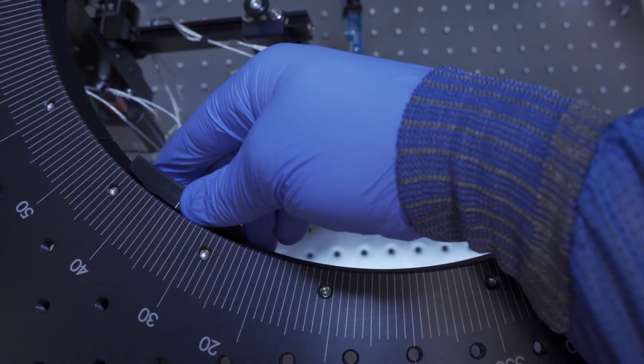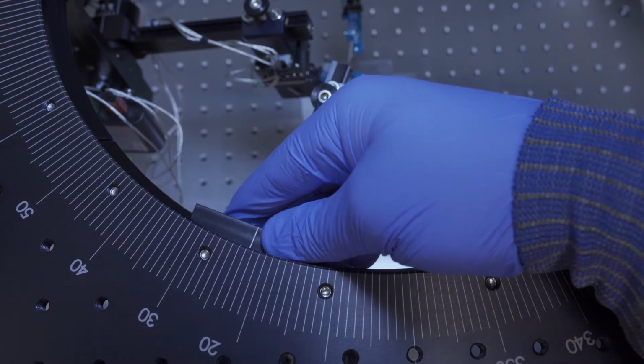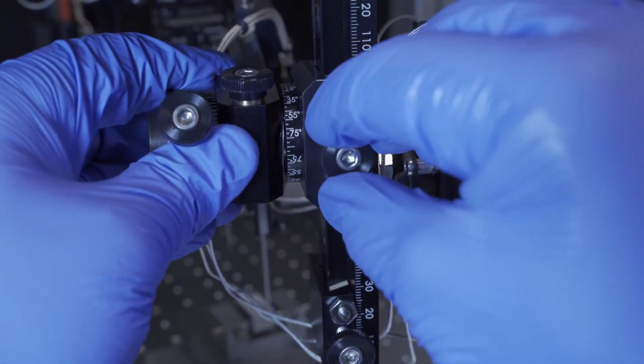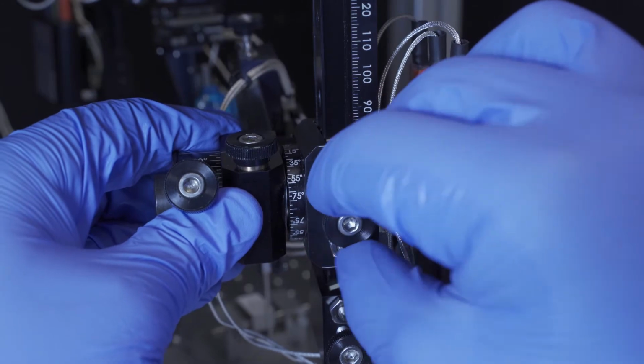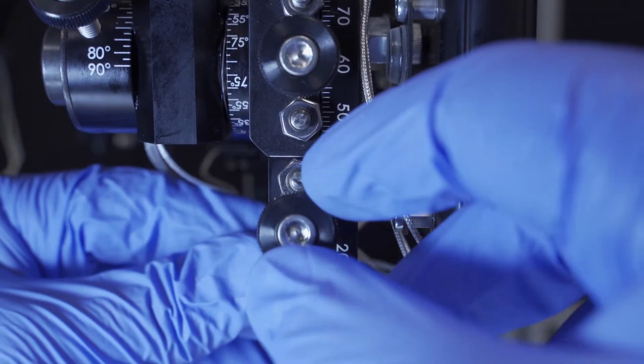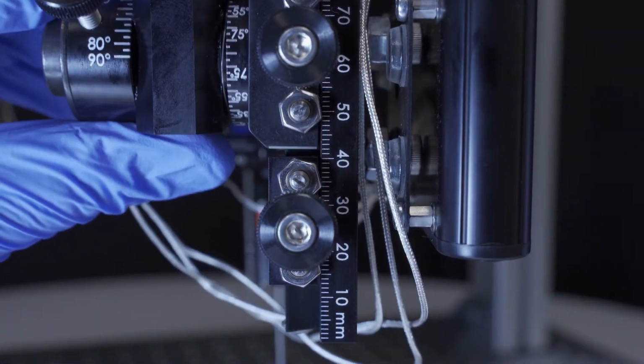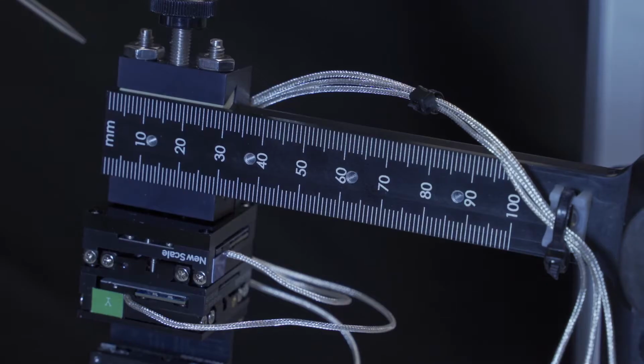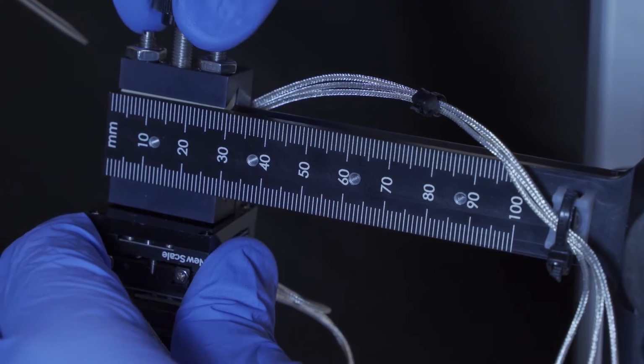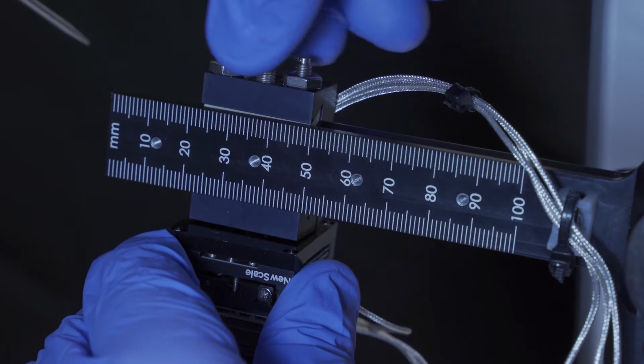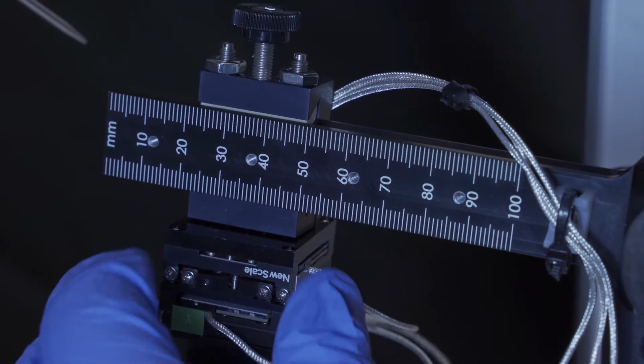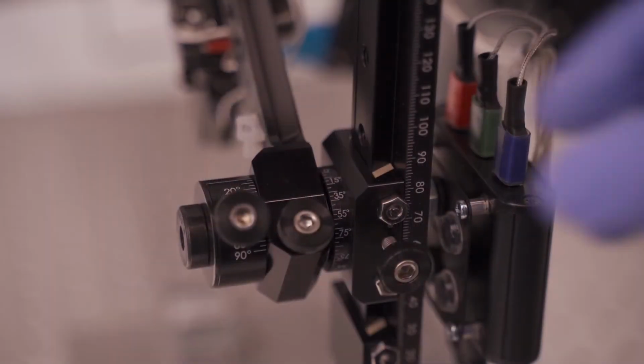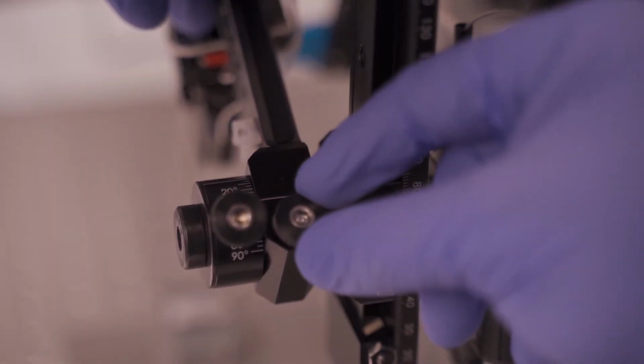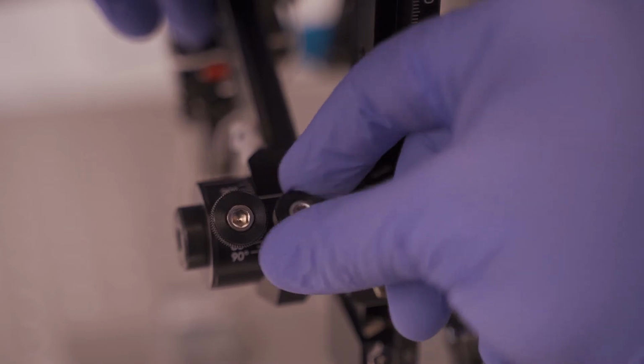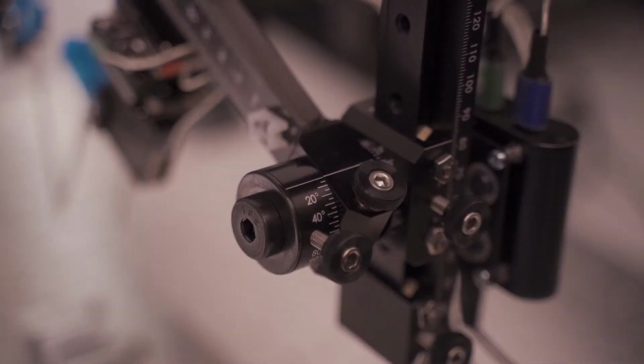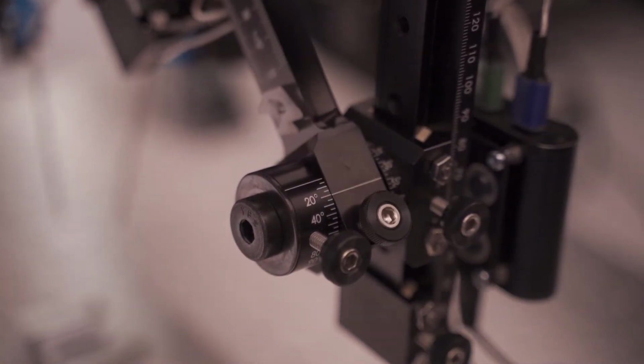You can adjust the polar angle of the probe by sliding the arm around the dovetail ring. You can adjust the vertical position by moving the arm along the vertical slide. An adjustable stop enables repeatable positioning. The horizontal position of the probe is also adjustable by moving the arm along the horizontal slide. Finally, you can adjust the insertion angle of the probe. This axis also has an adjustable stop.